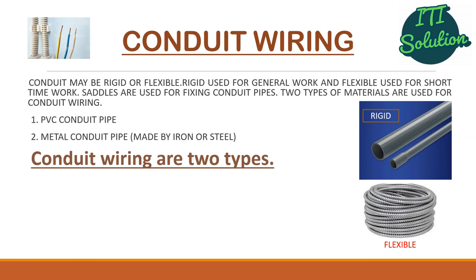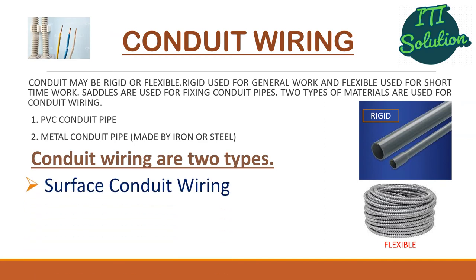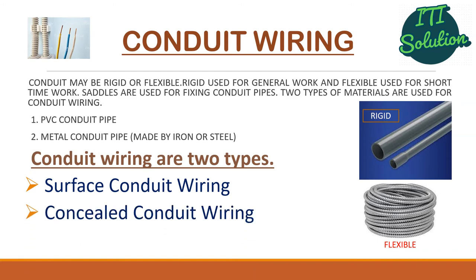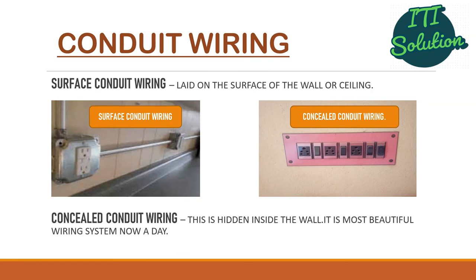Now we discuss about conduit wiring. Conduit may be rigid or flexible. Rigid type is used for general work, while flexible type is used for short-term work. Saddles are used for fixing conduit pipe. Two types of materials are used for conduit wiring: one is PVC conduit pipe and another is metal conduit pipe made by iron or steel. Conduit wiring is of two types: surface conduit wiring and concealed conduit wiring. In surface conduit wiring, the conduit is laid on the wall or ceiling surface.